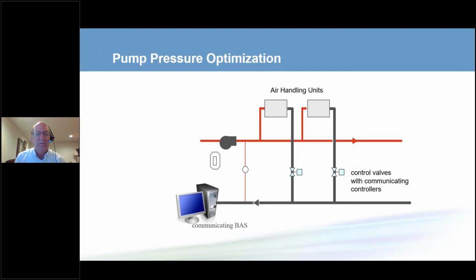In pump pressure optimization, we have a communicating building automation system or chiller plant control system that's communicating with the control valves. We get the signal from the control valves, and the signal we're looking for is: how wide open are you? Because if all the control valves are closed, we're putting energy into the pump producing pressure, and the valves are closing to reduce that pressure.